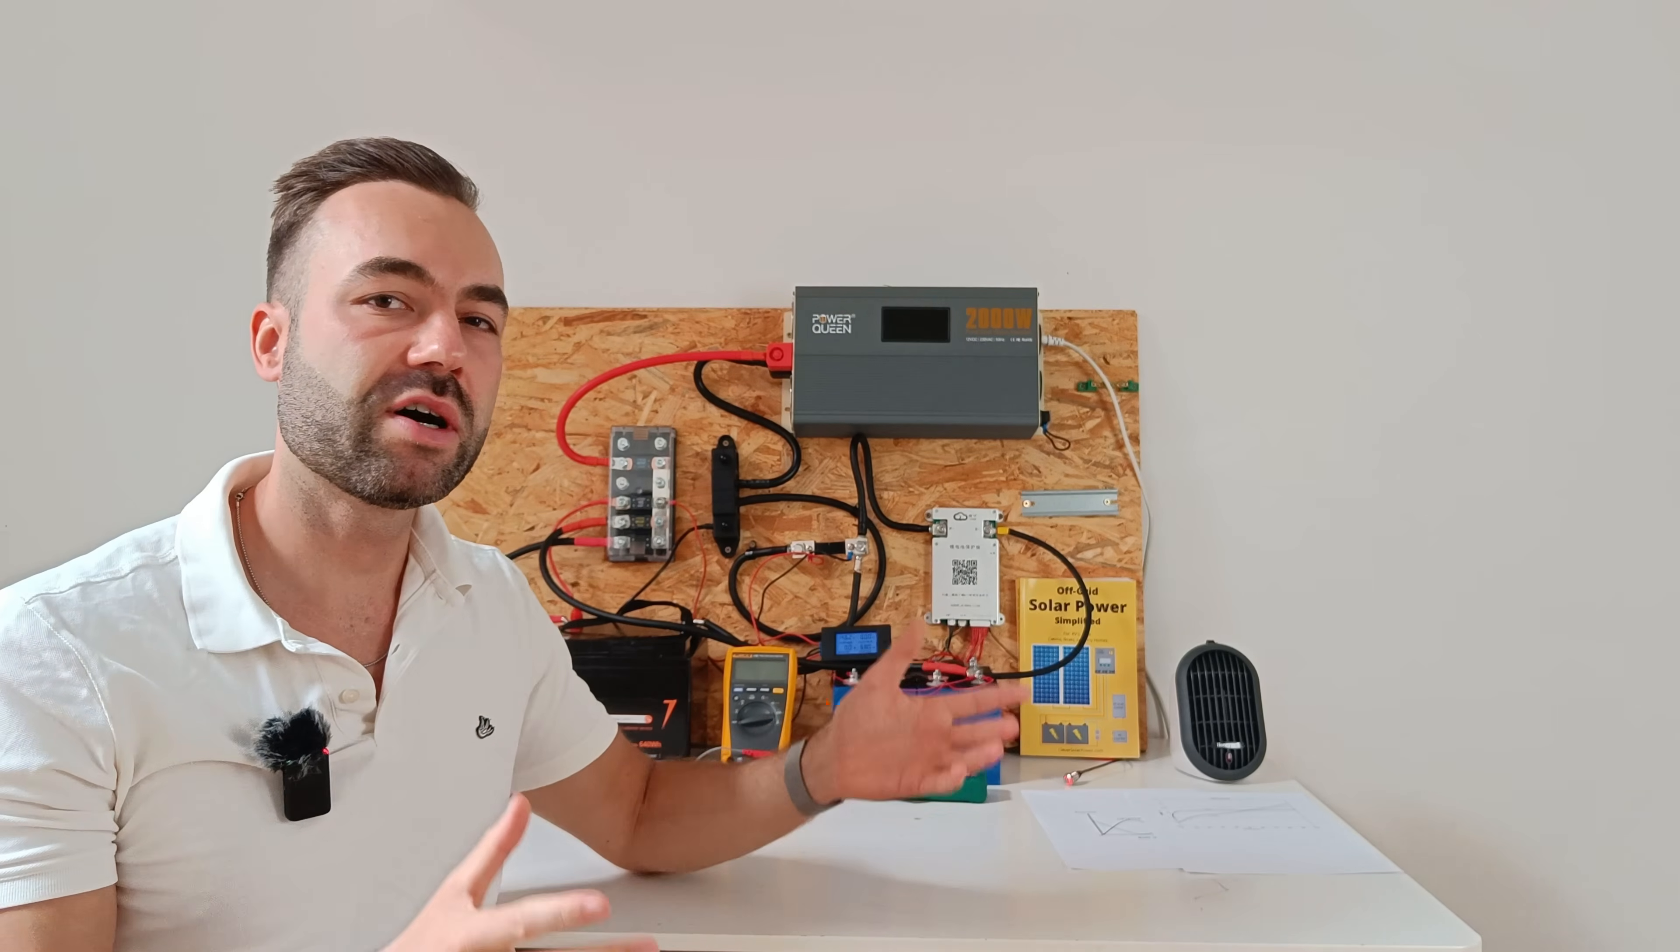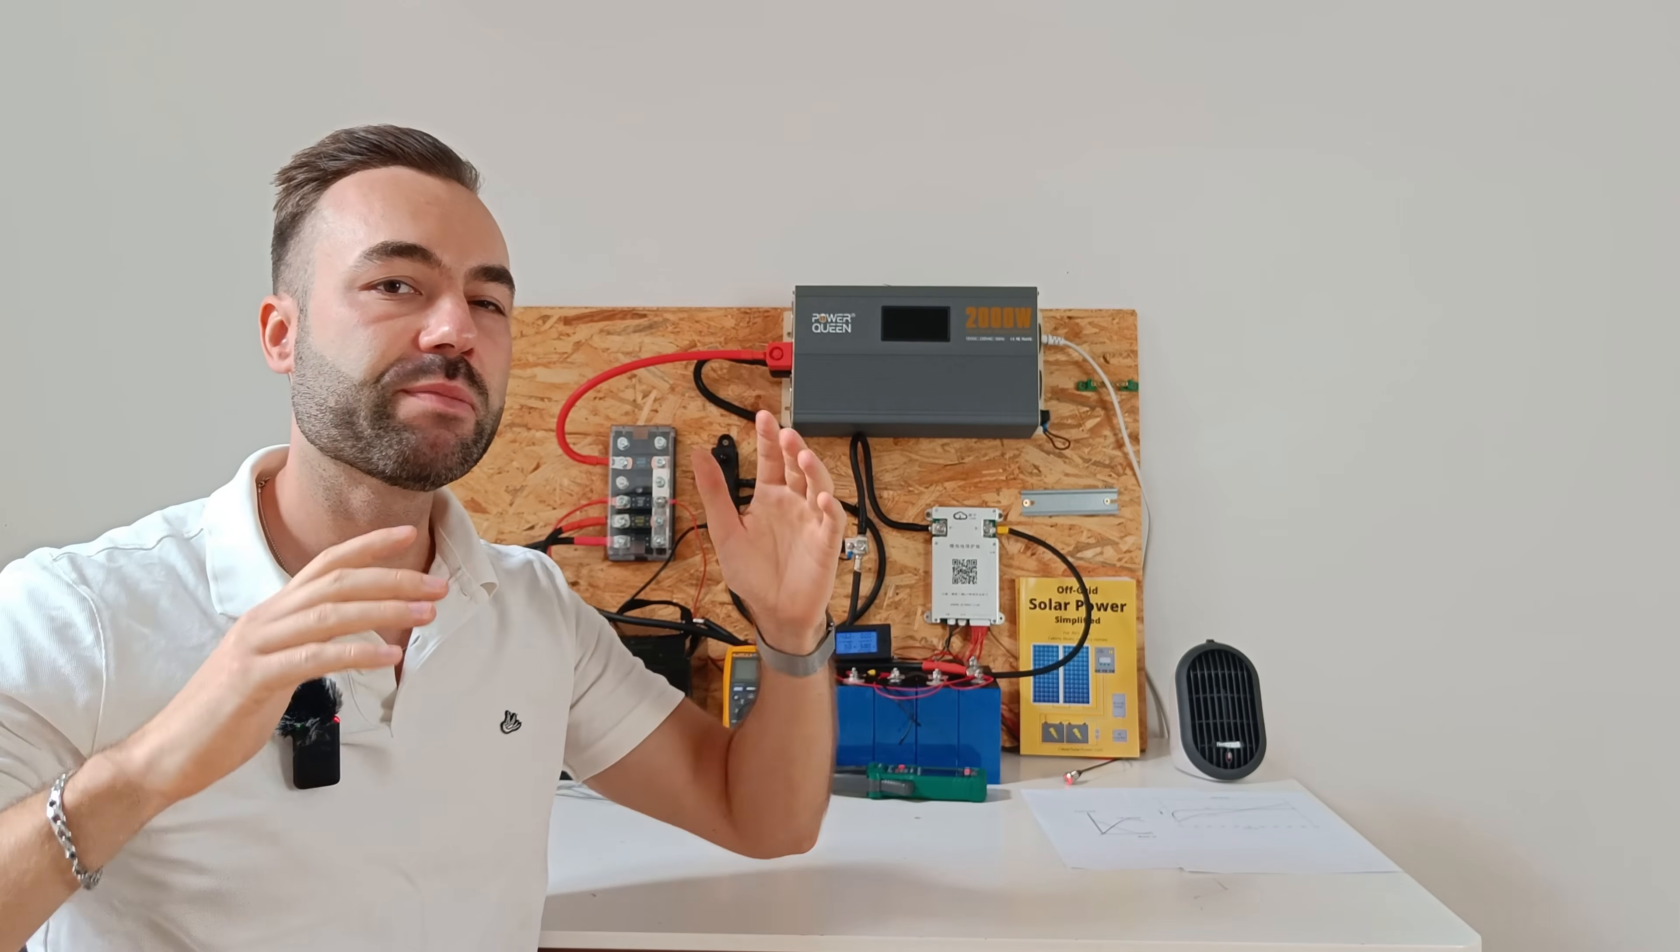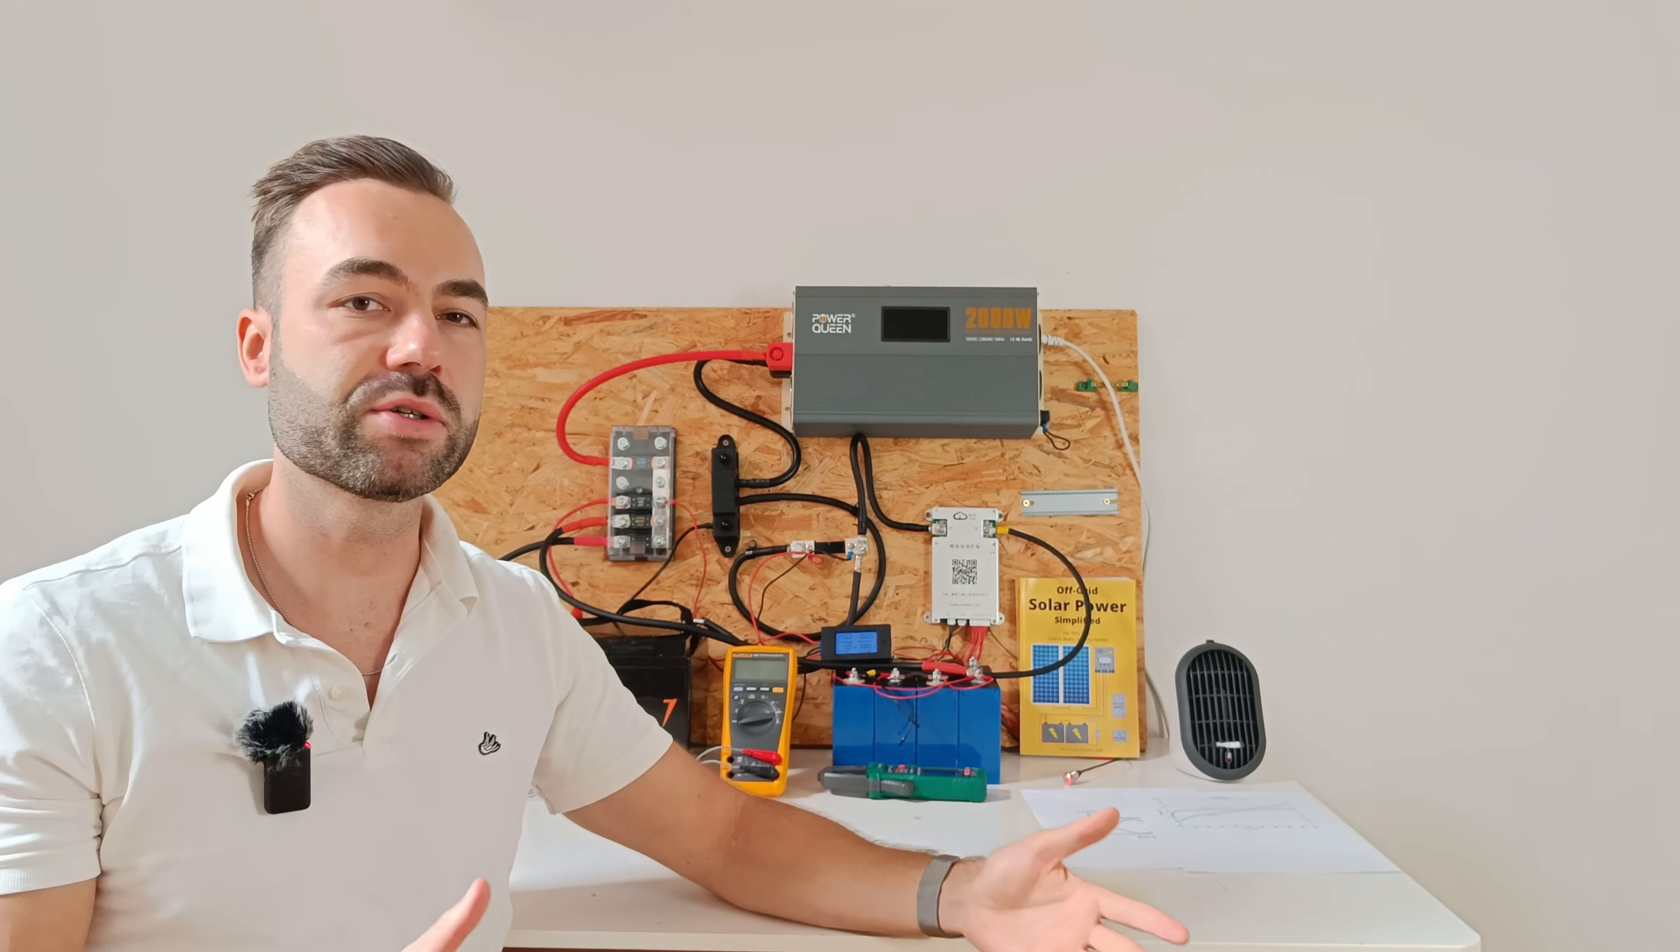Let me quickly talk about voltage. When you connect two or more batteries in parallel, no matter the chemistry, the batteries equalize to the same voltage. That means we have to match the voltage of the sodium ion battery to the one of lithium. Otherwise we will overcharge or under discharge the lithium battery, which is not good.